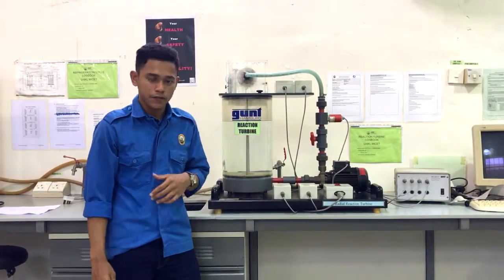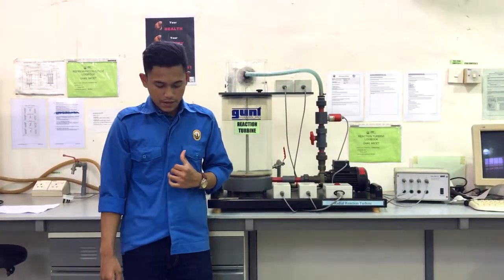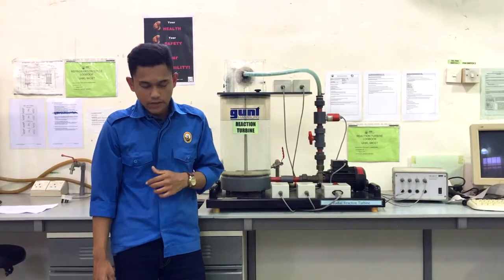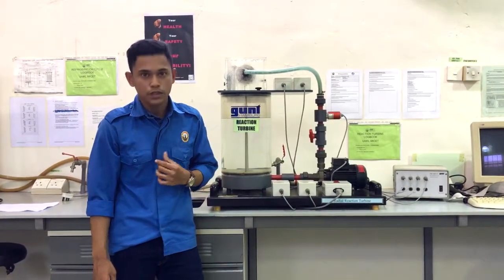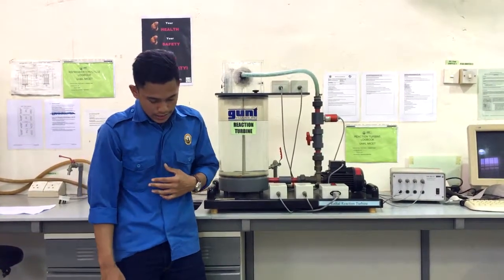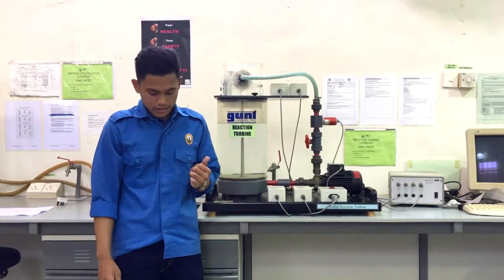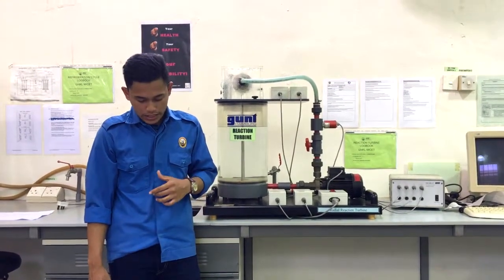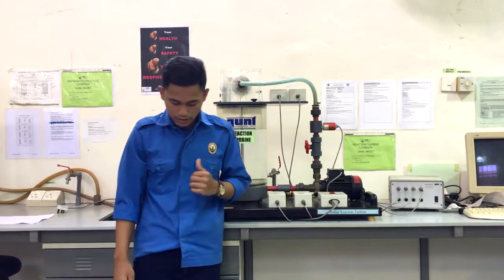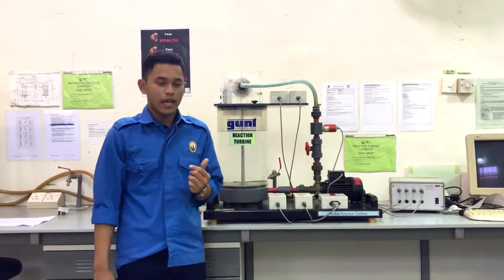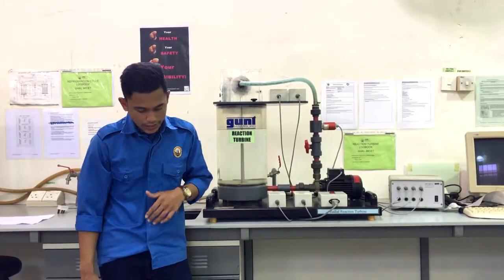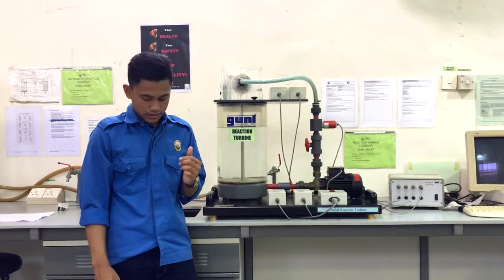And lastly, the draft tube. The water, after passing through the runner, flows down through a tube called the draft tube. It increases the head of water equal to the height of the runner outlet above the tail race, and it also increases the efficiency of the turbine.